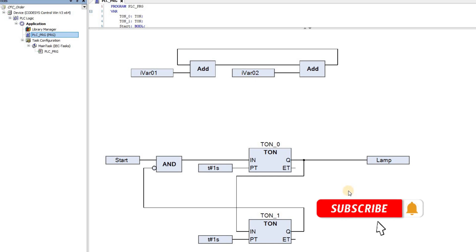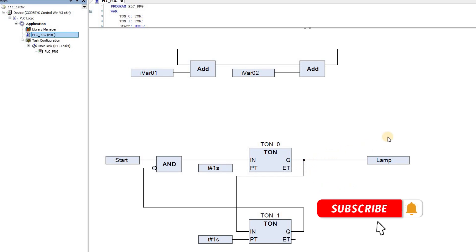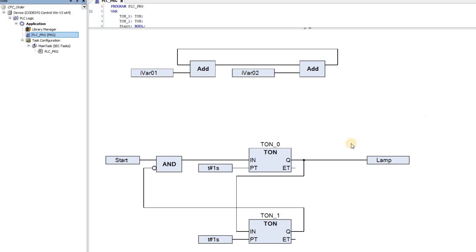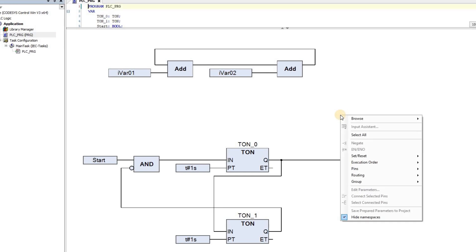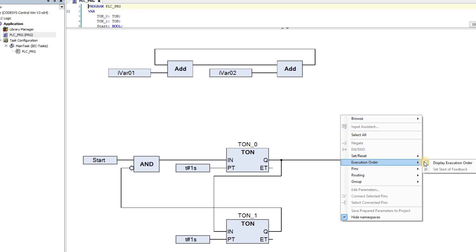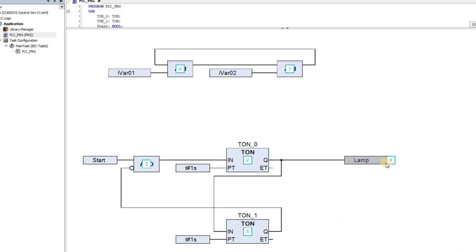And if there is more than one network, like the one that we have here, the execution order is based on the topological position of the networks. We can display the order of the execution of the blocks by right-clicking in an empty area in the editor, choosing Execution order, and then Display Execution order. The order in which the blocks are being executed is now shown by numbers, starting from zero. If you click on the editor again, the numbers will disappear.